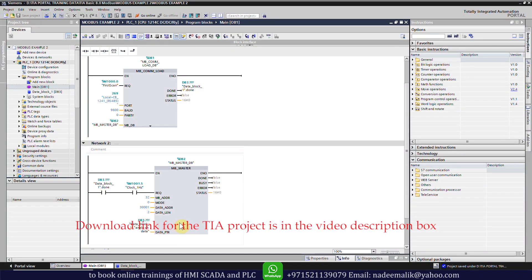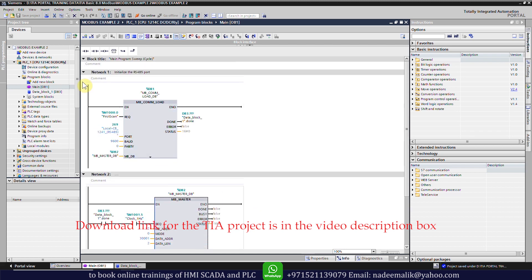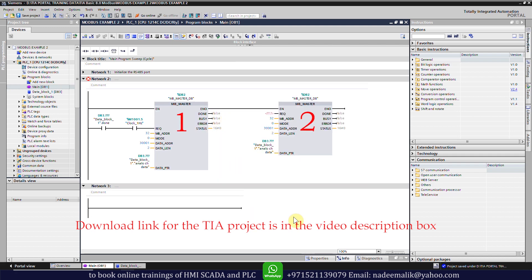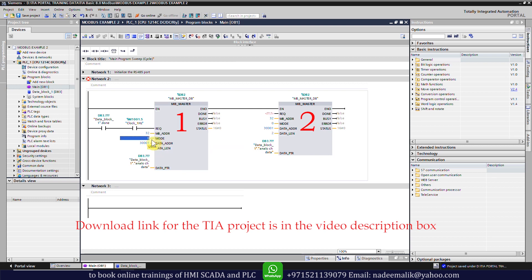First we will open the same project from Part 1 in TIA portal. We will copy the MB Master function and paste it on the ladder, so now we have two MB Master functions in the program. In the first MB Master function the mode is zero, as we want to read data registers over Modbus.